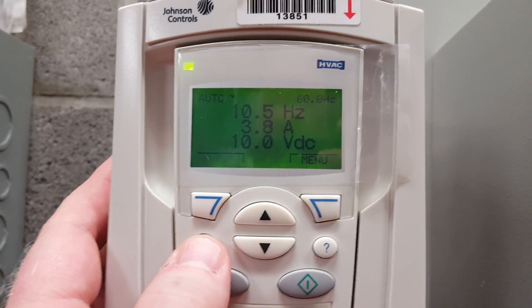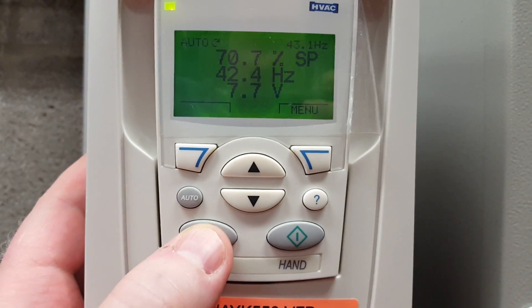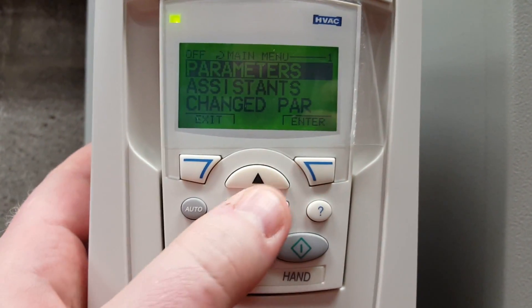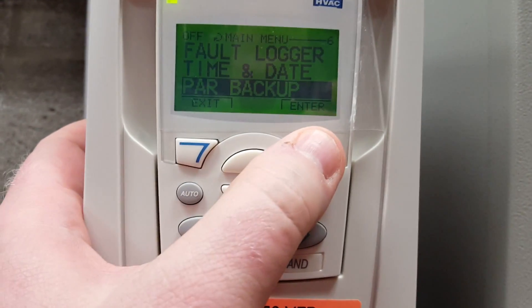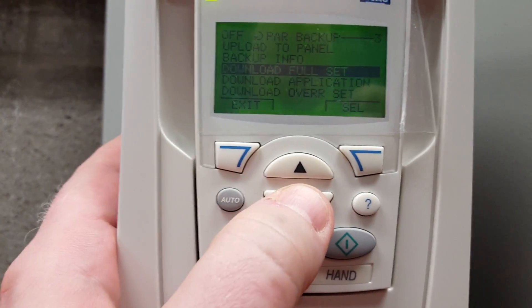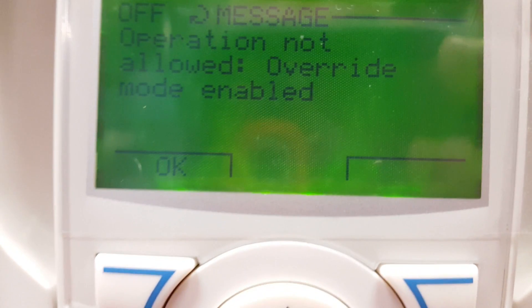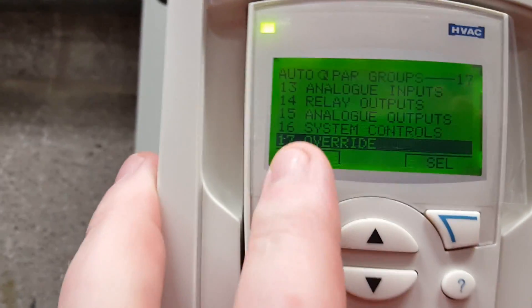Once you back all the way out, press the auto button and the drive should restart with no problem. Now, if the override mode is enabled, you will get an error if you try to download. This is common with the York drives as well as Johnson Controls drives, which are ABB drives with a York or Johnson Controls sticker.